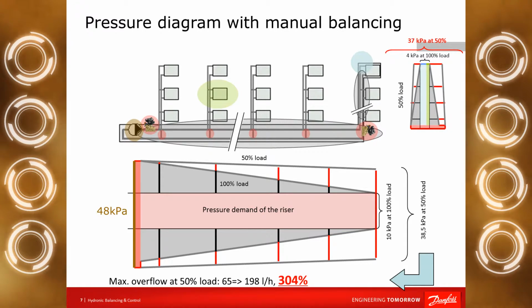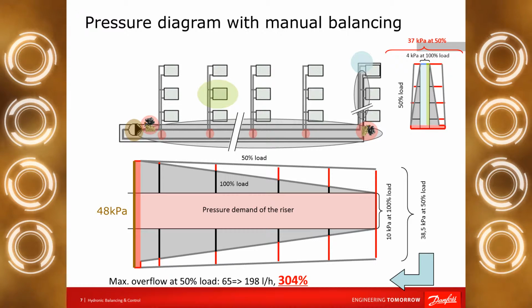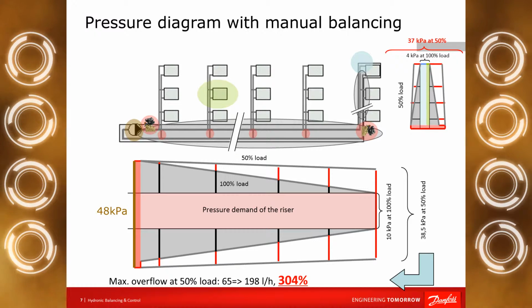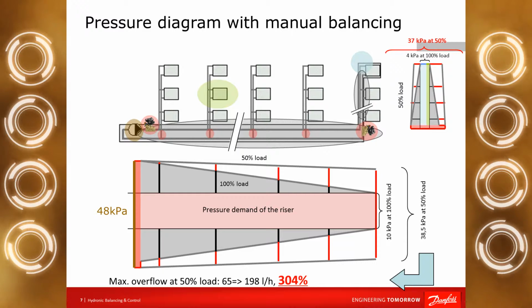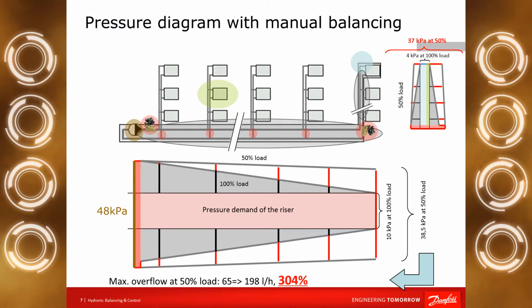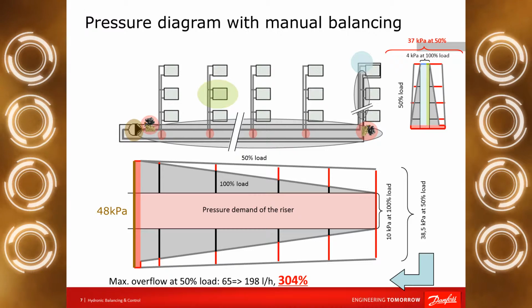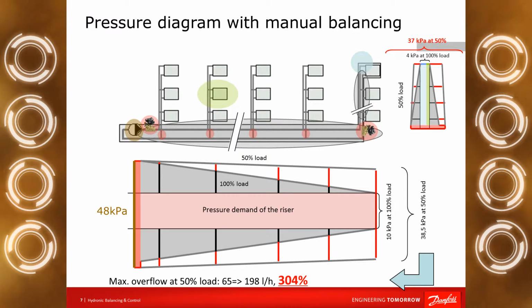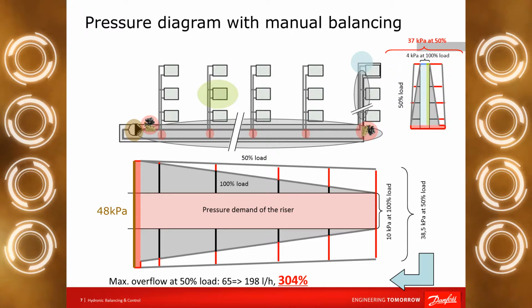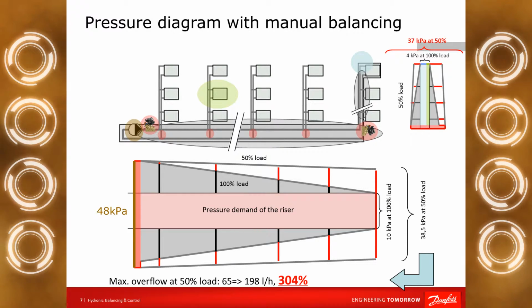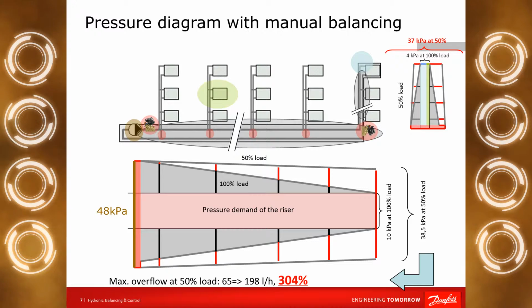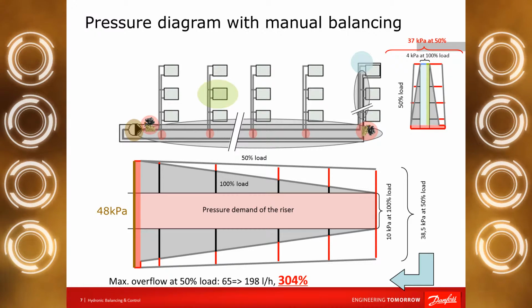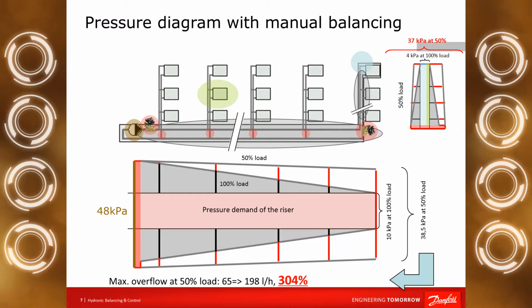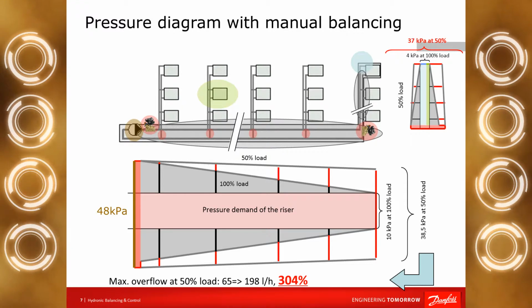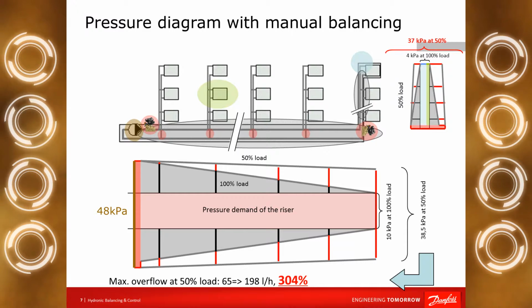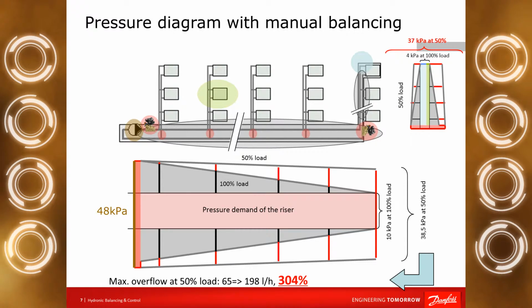We can see clearly we have much bigger available pressure in the beginning of the system compared to the end. Therefore, we have to use the manual balancing valve, in this application at least, to reduce the overpressure in the bottom of the riser and also the overpressure in front of the radiators with the presetting valves. In this case, we can say this system is working properly when we have 100% flow rate in the coldest outdoor temperature and without internal heat gain. Can we be satisfied with it?